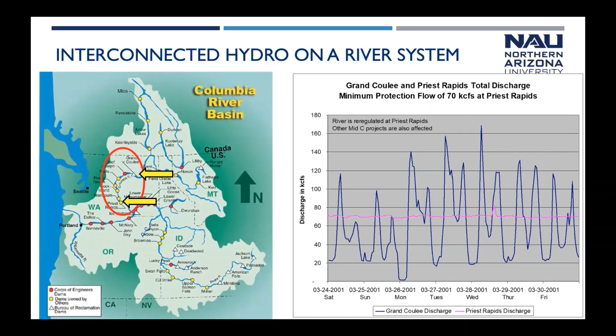This plot on the right shows the discharge from Grand Coulee during a week in 2001. The dark blue line goes up and down as Grand Coulee generates not much at night and a lot during the day, during peak hours. The red line in the middle is the discharge from Priest Rapids downstream, and you can see that's very constant. So what happens between Grand Coulee and Priest Rapids is that the distribution of water is re-regulated—what comes out of Priest Rapids is very constant. It's constant because south of Priest Rapids there's a free-flowing stretch of the Columbia River where a lot of salmon spawn, and environmental regulations make it precise in terms of how the water comes out. So Priest Rapids doesn't have much flexibility, whereas Grand Coulee does.